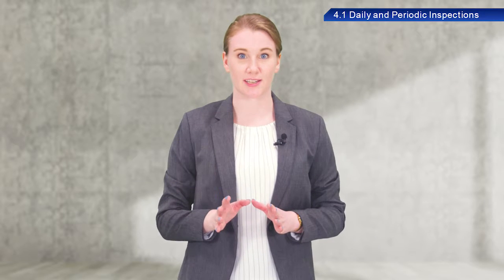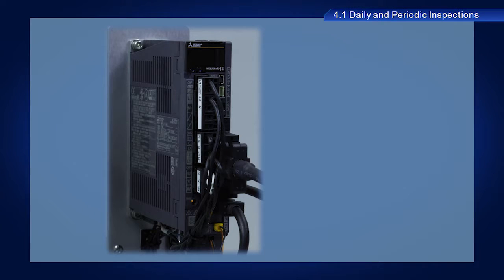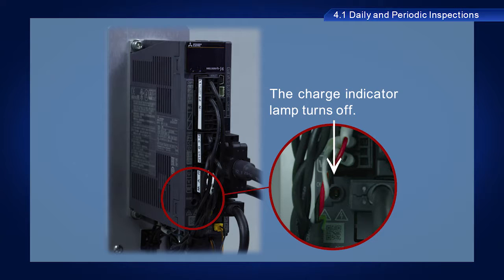A note of caution here: Some internal components store electrical charges for some time after the power is turned off. Wait until the charge indicator lamp turns off before inspecting internal components of servo amplifiers.